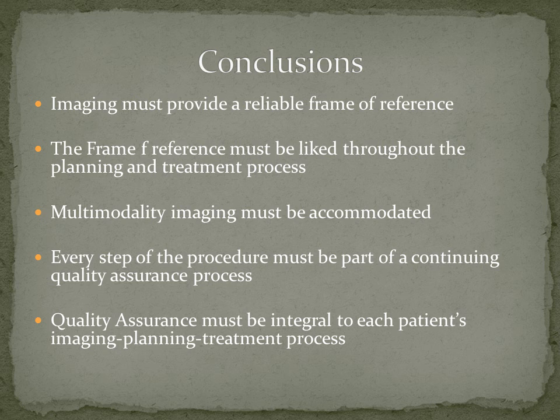Things get bumped, things get broken. Our systems are designed so that if you drop a head ring and it is not correct anymore, if you drop a CT localizer and it gets misadjusted, they will fail our QA tests as we process these images. And that does happen. We'll get a phone call from Russ saying, you better come down here.